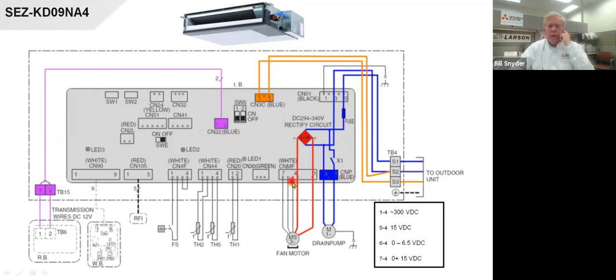So if you check between 4 and 5, you should read about 15 volts all the time. Between 6 and 4, you're getting between 0 and 6.5 volts DC, and terminals 4 to 7, you would be reading somewhere between 0 and 15 volts DC. This is the circuit that sends the speed to the motor, and this is the circuit that responds back and says that I am turning. So it just gives you a little bit of an idea of how that works. This one also has a drain pump or a lift mechanism. It's not really a pump, it literally lifts, because this drain is on the bottom of this, and this could sit against the ceiling. It literally lifts the water out of here and slings it out the side. It doesn't pump it, it just slings it out the side. So you would gravity feed from there.